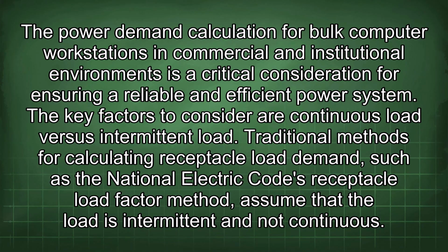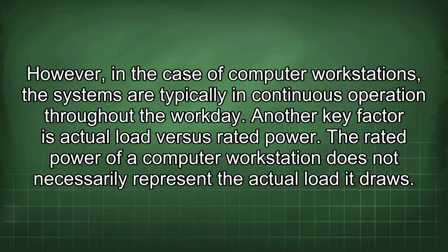Power demand calculation for bulk computer workstations in commercial and institutional environments is a critical consideration for ensuring a reliable and efficient power system. The key factors to consider are continuous load versus intermittent load. Traditional methods for calculating receptacle load demand, such as the National Electric Code's receptacle load factor method, assume that the load is intermittent and not continuous. However, in the case of computer workstations, the systems are typically in continuous operation throughout the workday.